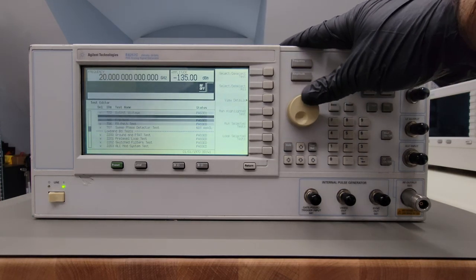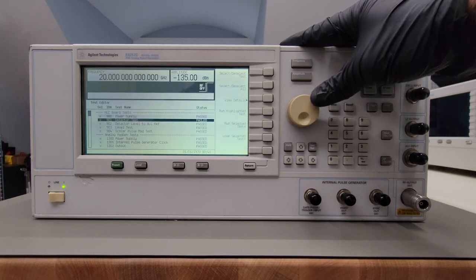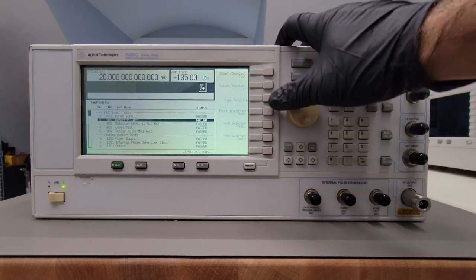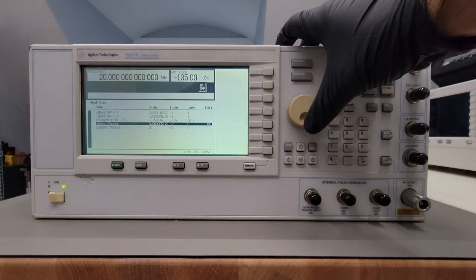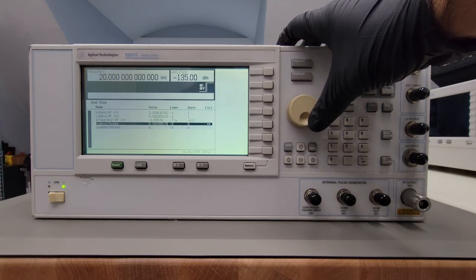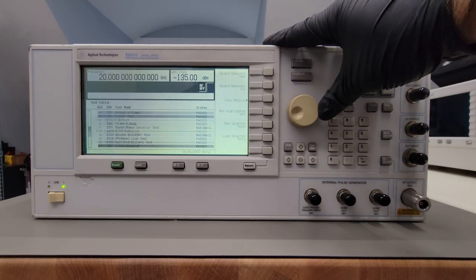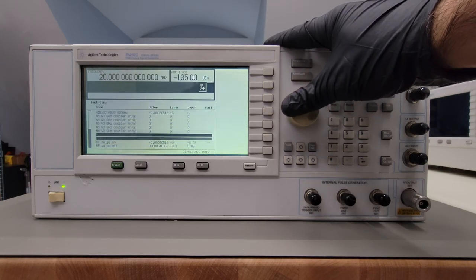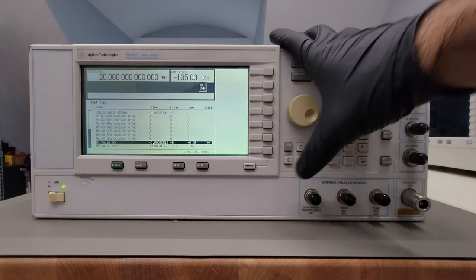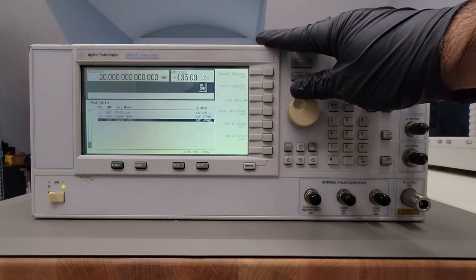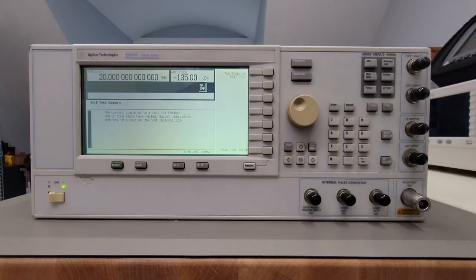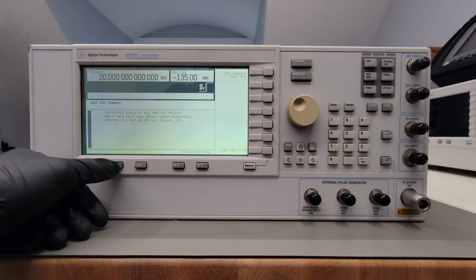We're seeing the same failures here. So if we go back to the top, we still have the 901 error here. View the details. High band max out, so that's still failing. We go down here, and our 1204 error, RF pulse on, that's also failing self-test. Everything else is fine.